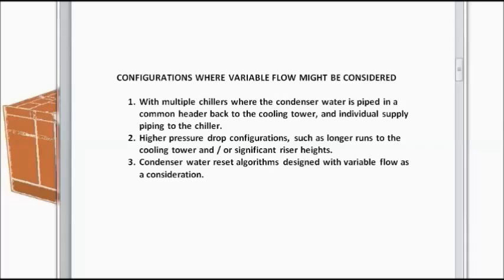But each chiller is supplied directly by its own pump in parallel with the other chillers. And number two would be where the condenser water piping pressure drops are high with long run configuration and significant riser heights to the cooling towers.